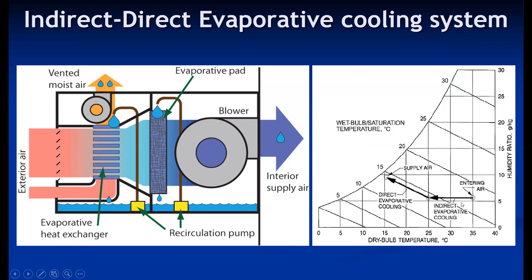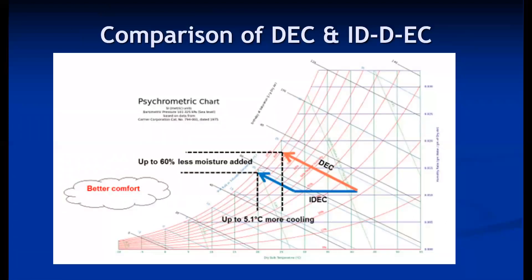Two psychrometric processes occur in the indirect-direct system: sensible cooling followed by cooling and humidification. Comparing with direct evaporative cooling alone, the indirect-direct system results in approximately 60 percent less moisture addition and about 5.1 degrees Celsius more temperature drop, providing better comfort conditions. This makes it a better option compared to direct evaporative cooling alone and even compared to a conventional package air conditioning system.